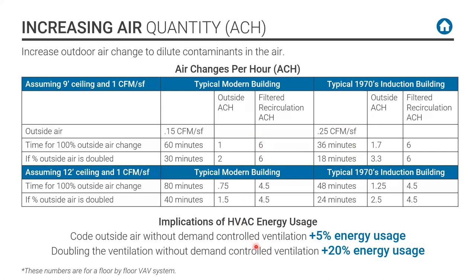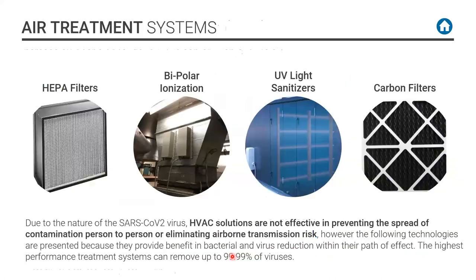And you say, what about energy use? And we've done an analysis actually of 2 buildings in one of the large cities. Bottom line is if you double the outside air, if your air handling systems can handle it, you could get up to a 20% energy usage increase, remember, of the HVAC energy, and just disabling demand control ventilation, about a 5% energy use increase. So let's talk about that. First, we've diluted. Now we'll talk about removal.